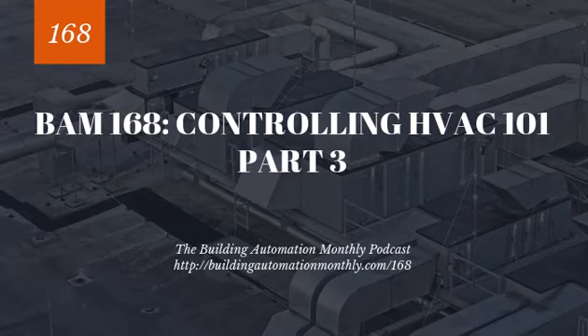Now, the one thing we have that is really different from hot water systems, and we'll discuss this in next week's episode, is that with hydronic chilled water systems, we have partial load. Typically, how we run partial load is that when load is lower than the range that a single primary chiller could efficiently handle, and when the load is higher than all of the primary chillers can handle, that's when we tend to use our partial load systems. They are typically independent of a primary system, meaning that they will typically have their own pumps, cooling towers, and valves that are sized to them.